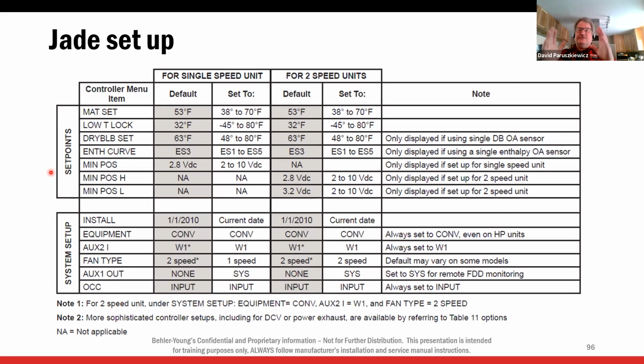And it'll take you to a little Jade looking control, which is interactive and allows you to go through all this stuff. You can force dampers open, turn compressors on. You can see what your enthalpy sensor is, what your outdoor temperature is, your damper position. You can drive your damper. So it's really a great control to work with. But when I get one, we have to set it up. And this is the call we always get on these. So we're going to take a look at this. This is pretty simple. We've got set points and system setup.